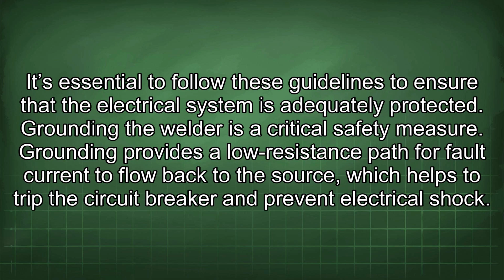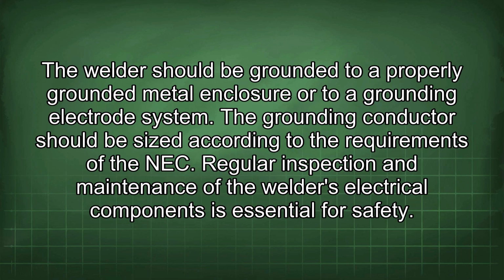Grounding the welder is a critical safety measure. Grounding provides a low resistance path for fault current to flow back to the source, which helps to trip the circuit breaker and prevent electrical shock. The welder should be grounded to a properly grounded metal enclosure or to a grounding electrode system. The grounding conductor should be sized according to the requirements of the NEC.